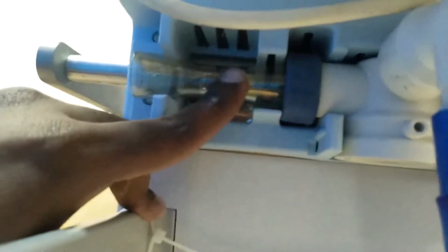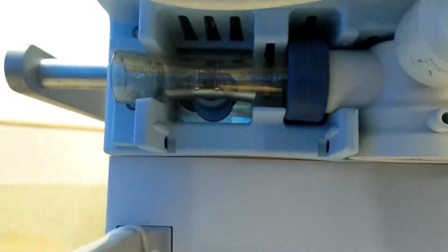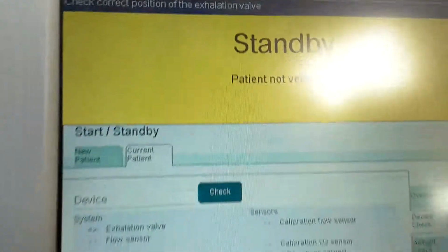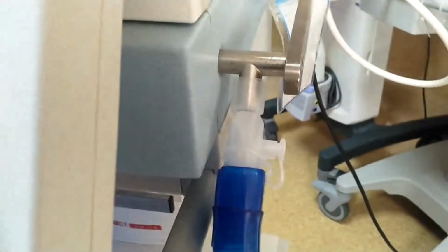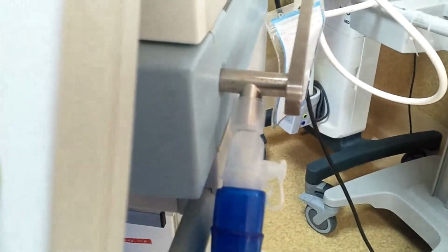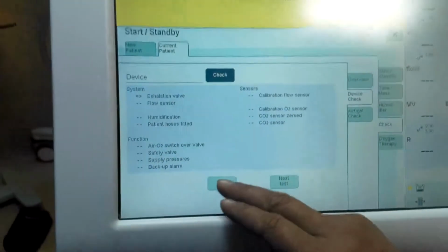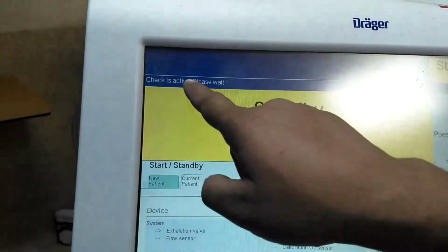This is the flow sensor. The next question will be whether the flow sensor is connected properly. So this is how you remove, and this is how you connect the flow sensor. It says check correct position of the exhalation valve, and we give OK. Next it says connect the test line to the Y-piece. Instead of the Y-piece, we will just cheat the machine by connecting it to a closing plug. Now we give yes, and now it is testing.